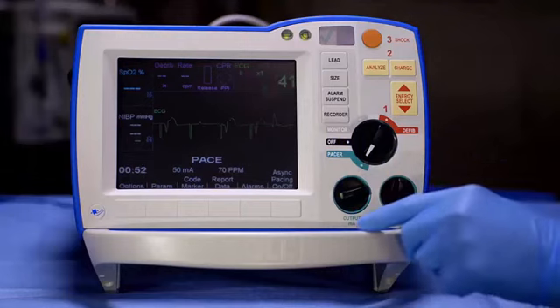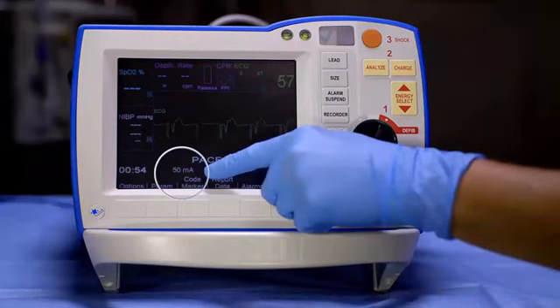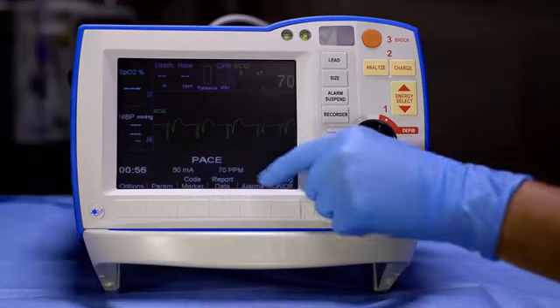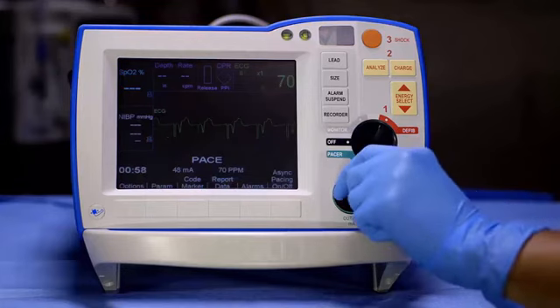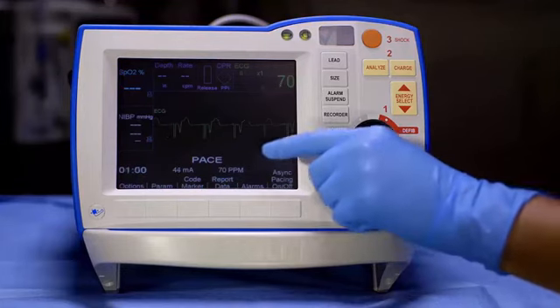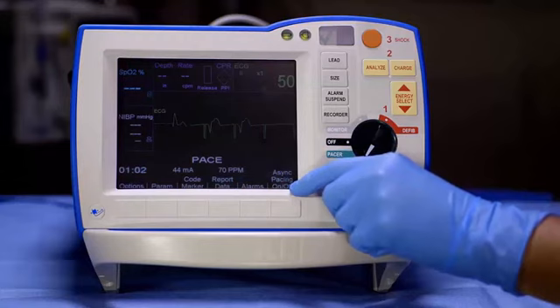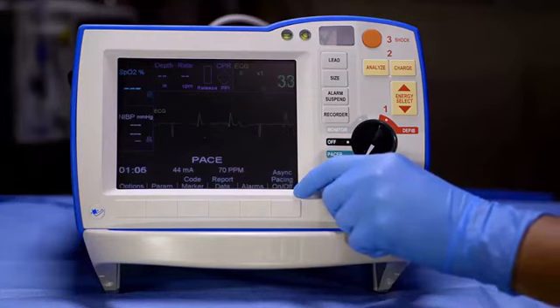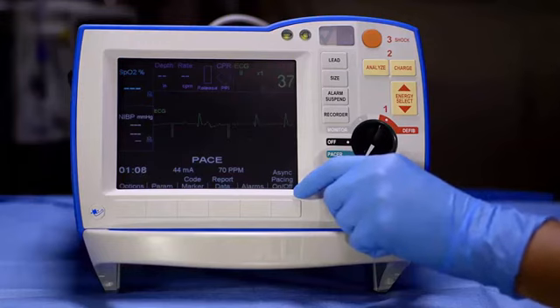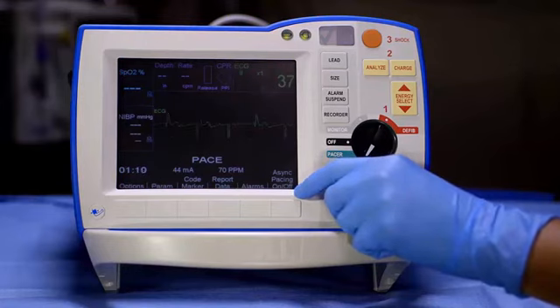Usually, when obtaining capture, you will overshoot the patient's threshold. If this happens, decrease the output slowly until you just lose capture. The minimum output that obtains capture is the patient's threshold. Once you have determined the pacing threshold, set output to 10% above that.